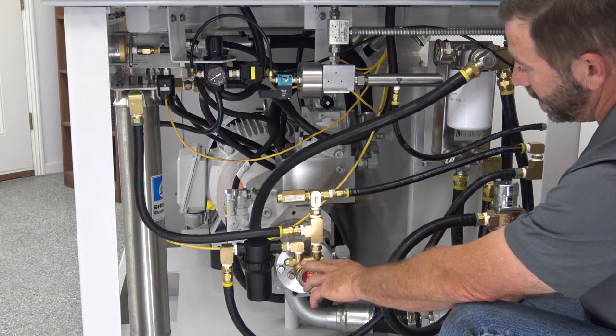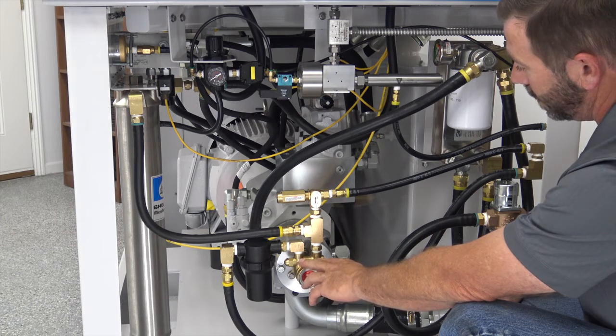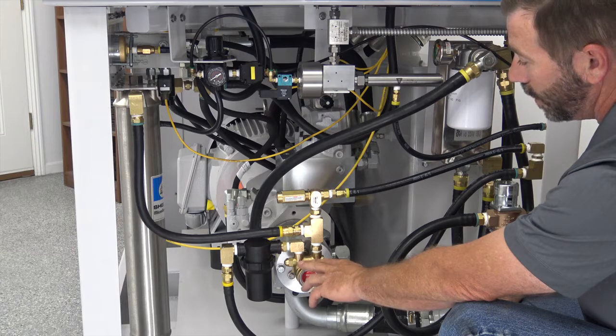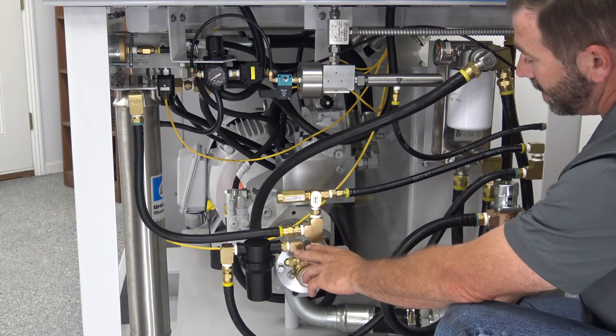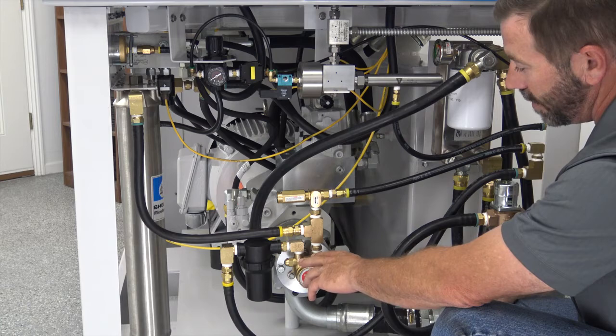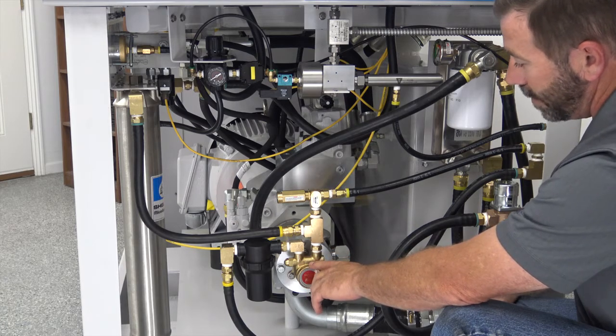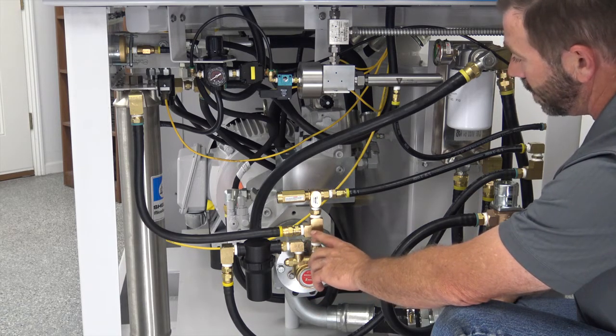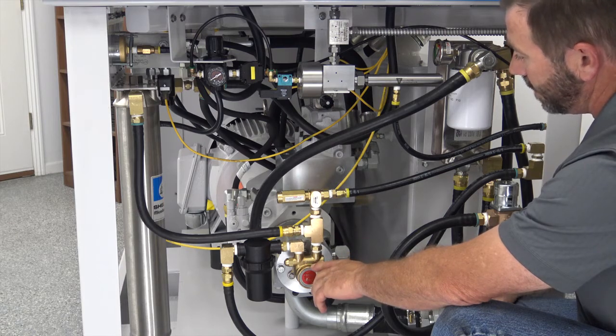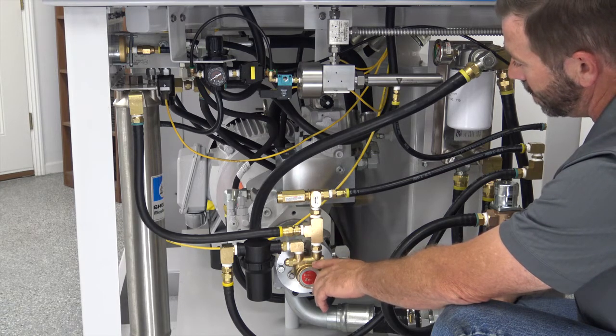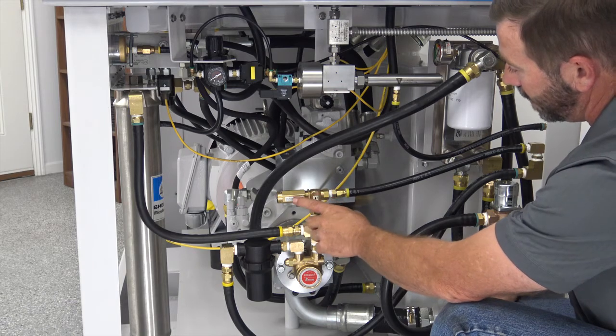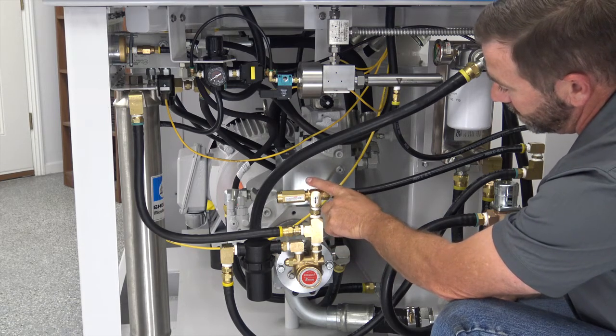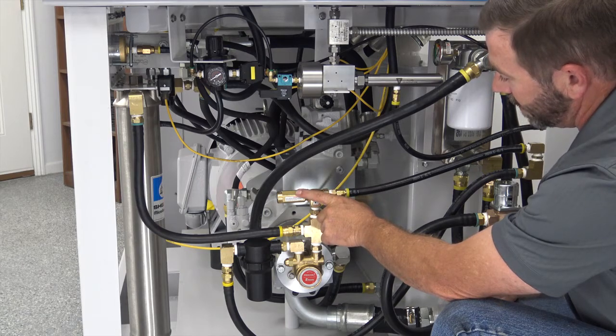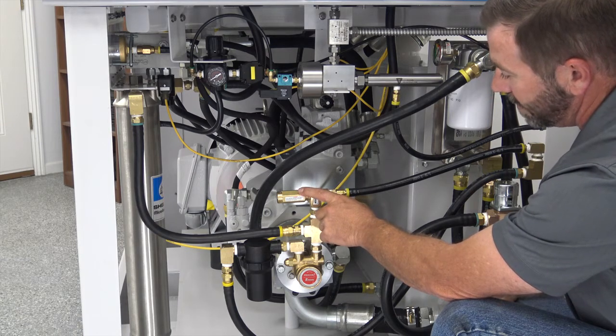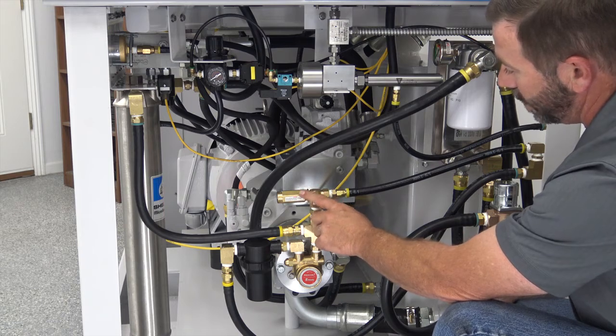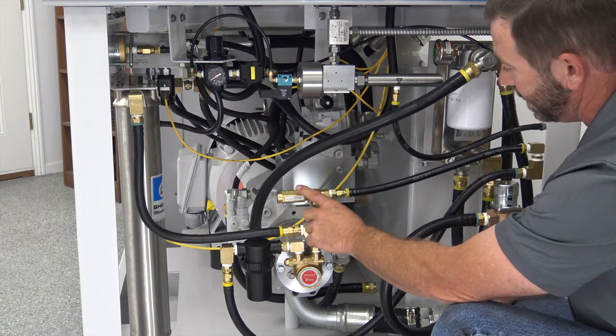This is what creates the low inlet water pressure on your pump going into your cylinders. These are set at different pressures depending on the unit you have. You'll want to check your manual for specific water pressures on specific units. If you need to increase the pressure of the booster pump, you always do this through the relief valve up here. You break the small jam nut loose, and you turn this clockwise to increase the pressure, counterclockwise to decrease the pressure.